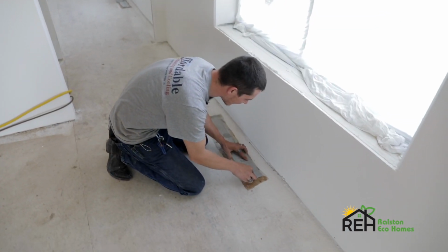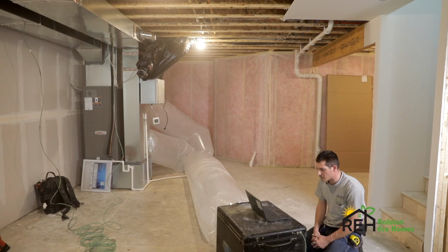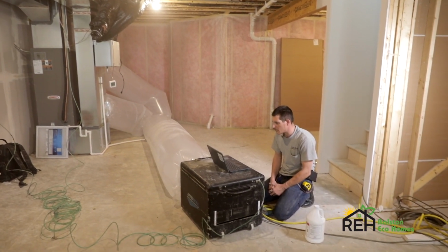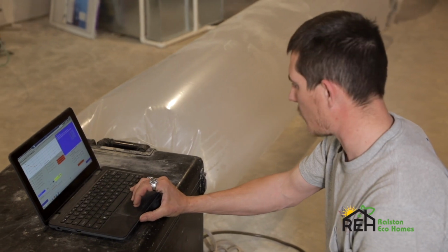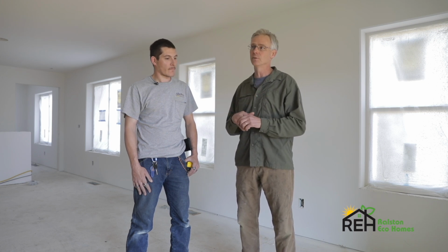Yeah, very impressive. And again, we did that by pressurizing the system and introducing an aerosolized sealant that found all the little cracks and holes, the tiny little things that you can't see and the bigger holes, and sealed those up. So that we now have a heating and cooling system that's going to deliver hot air or cold air, whichever we choose, the amount we want to each room. So this is going to be a comfortable house. And the system is going to be efficient. We're not going to be heating places we don't want to or cooling places we don't want to. The system's going to be working as efficiently as possible. And then also because it's tight, we're not going to be introducing contaminants into the system. So the house is going to be efficient, comfortable, and healthy.